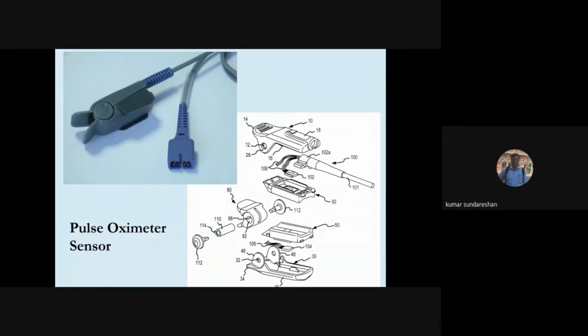It's so simple, but very effective. Nowadays, you have these small portable devices that have come into the market, where you just have to plug into your finger, and on the other end, you have the display which gives you the oxygen saturation levels along with the pulse rate and things like that. But when it comes to the construction of this probe, it's very complicated. Though it may look simple, there are so many sub-assemblies inside. You will have to place the light sensors appropriately. So choosing the right sensor, choosing the right part becomes very, very critical here. Because this is so commonly used, the wear and tear factor has to be kept in mind.